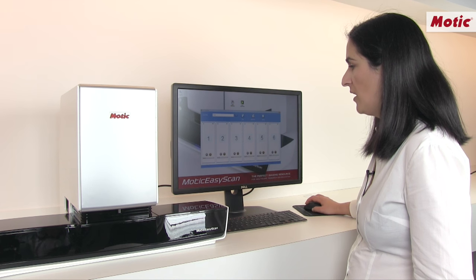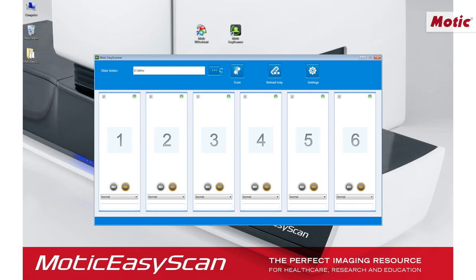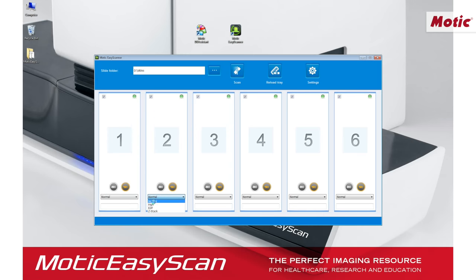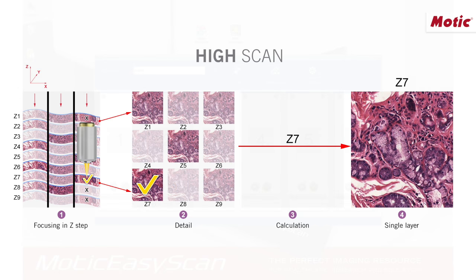For each slide we can select the magnification and the scanning mode. We can choose between four alternative scanning modes. The first option is the normal scanning mode — in this case, the system detects the focal plane on each field and captures the image. Then we have the high scanning mode, where the optics goes through several focal planes on each field but selects the one with more information.